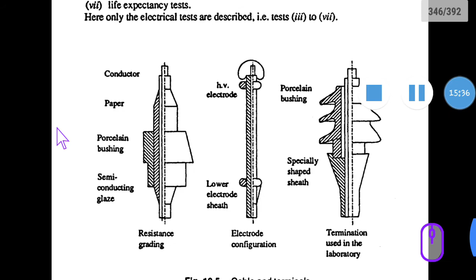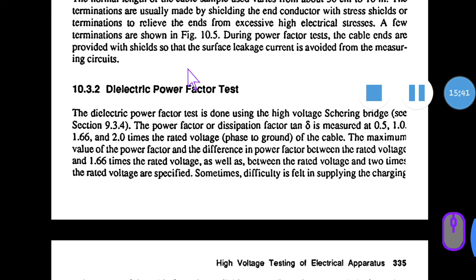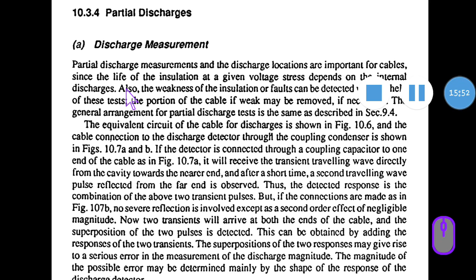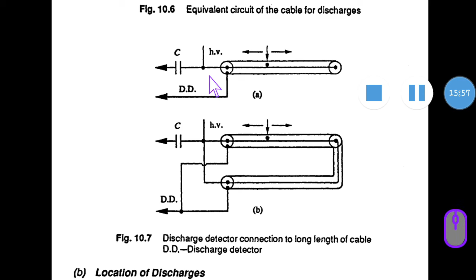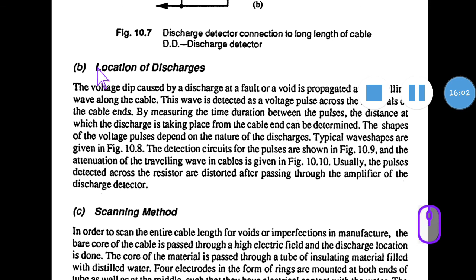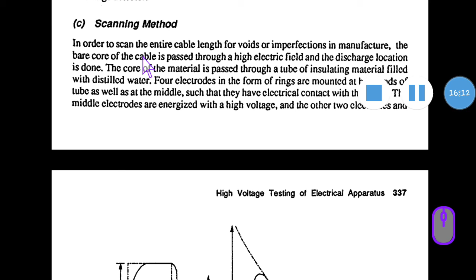Testing of cables we have done. First is preparation of cable samples, and second is the dielectric power test using a Schering bridge, and high voltage testing on the cables, applying different voltages. Partial discharge, internal discharge, we check what type of voids are within. One end of the cable is connected to the discharge detector and coupling condensers, and the location of discharge is checked, where exactly it takes place within the cable. In the scanning method, they put the cables in a particular solution and check whether they will withstand that much voltage or not.